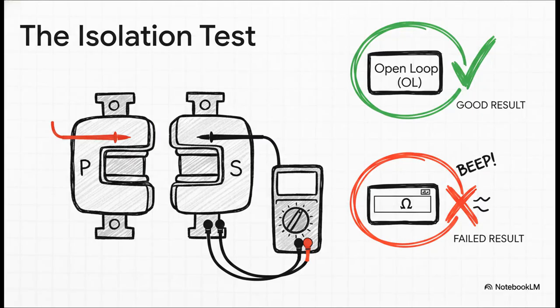And here's how simple it is. Take one of your multimeter probes and put it on any pin on the primary side. Now take the other probe and touch it to any pin on the secondary side. Now listen up, because this is the important part. For a good transformer, your multimeter must show open loop, OL, no connection, nothing. If you hear a beep from your meter, if you see any resistance reading at all, it's game over. That means the transformer is internally shorted and it has failed, period.